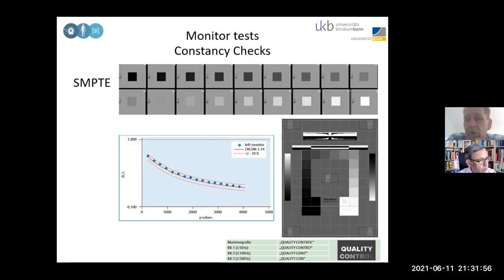If you have a microcalcification which is very young, so it has not been there for several years, so the calcification has not yet gotten more CaCO3 and still has some lipids inside, then the density is actually very, very close to the tumor value. And then 10 Hounsfield units difference could be the difference between microcalcification and tumor. And if you then have a noise value which is already 8, and you would like to see a signal of 10, I mean, I'm not very good in statistics, but you could easily figure out that if you have a bad signal to noise ratio in your phantom, which is actually extremely homogeneous, and then you will see in a real image a difference of 2 Hounsfield units, you will have a hard time.